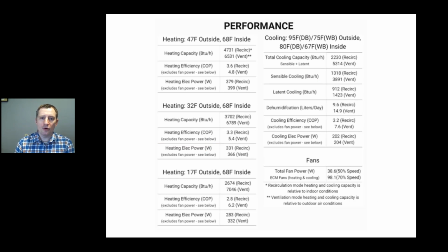Some performance numbers for the CERV, and you can find these online. There's a lot of detail here, but because it is a heat pump, we have both the capacity, COP levels, and input power for different outdoor conditions for heating and then cooling as well. So you can see at below freezing, the CERV is still close to a COP of 3. So it's a very efficient system.